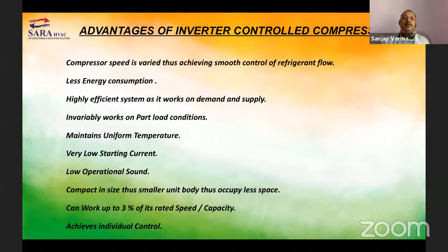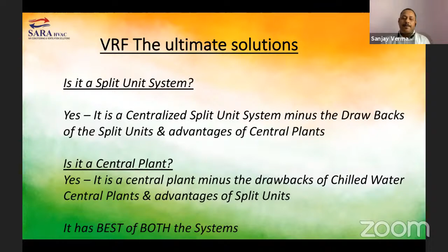Now, someone will ask, is it a split unit? Yes, it is a centralized split unit system, minus the drawbacks of split units and with the advantages of central plants, because we are going to save location for the many outdoor units which come with split AC for smaller systems. Then the second question, is it a central plant? We can say yes, it is a central plant, but again minus the drawbacks of a chilled water plant, where we need a larger place for the central plant, and again with the advantages of split units, like indoor units with smaller capacities. So this is the best combination. The VRF is the best combination of split unit and central plant advantages. So this is the best of both systems.